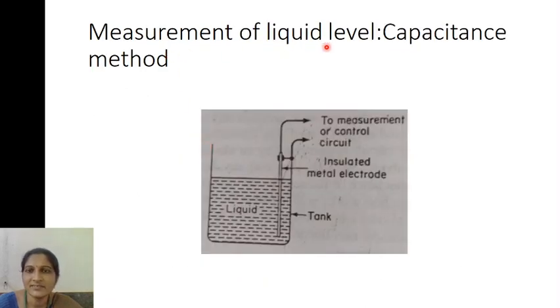Next one is the measurement of liquid level. For the measurement of liquid level, you use the capacitance method. This is the tank which contains the liquid. To measure how much liquid is in the tank, you place a metal electrode here. This metal electrode acts as one plate of the capacitor, and the tank acts as the other plate. A capacitor consists of two plates separated by a dielectric medium. So there is a distance between these two plates, which is the dielectric medium. If this is connected to a measurement control circuit, it measures how much capacitance there is. So this is the measurement of liquid level by using the capacitance method.